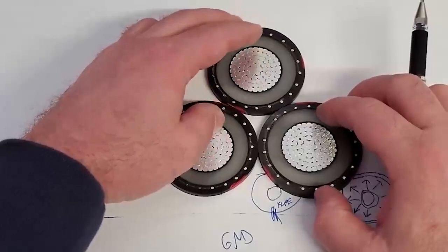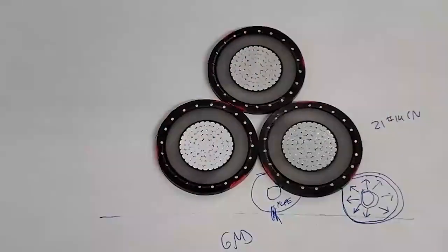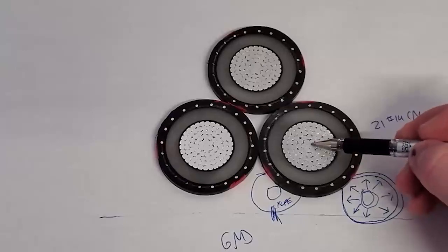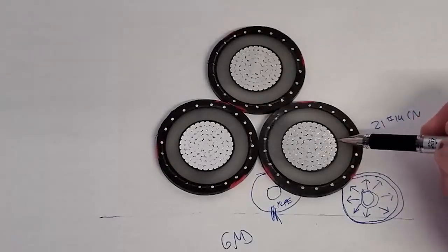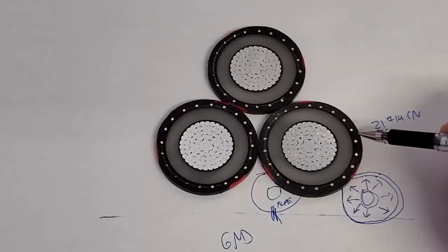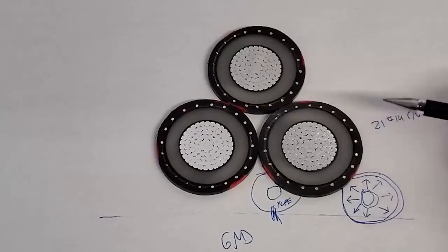So anyway, that in a nutshell is the 35 kV cable. I could talk 2 days straight on this stuff. That's really just high level. Again, your current carrying conductor, your conductor shield, your insulation shield, your concentric neutral layer, and your jacket.